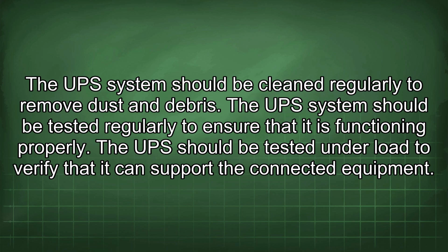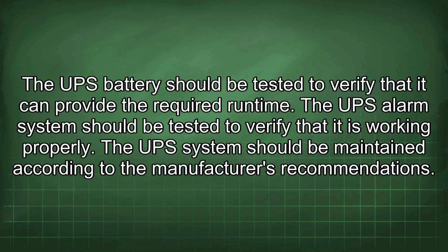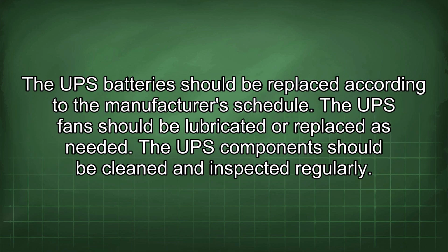The UPS system should be tested regularly to ensure that it is functioning properly. The UPS should be tested under load to verify that it can support the connected equipment. The UPS battery should be tested to verify that it can provide the required runtime. The UPS alarm system should be tested to verify that it is working properly. The UPS system should be maintained according to the manufacturer's recommendations. The UPS battery should be replaced according to the manufacturer's schedule. The UPS fan should be lubricated or replaced as needed. The UPS components should be cleaned and inspected regularly.